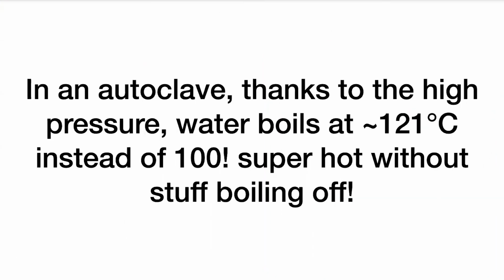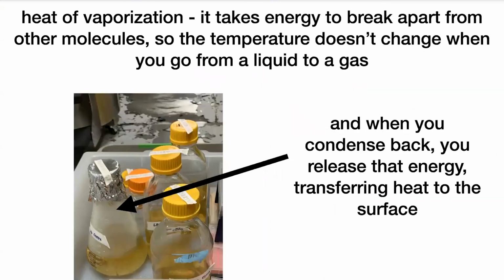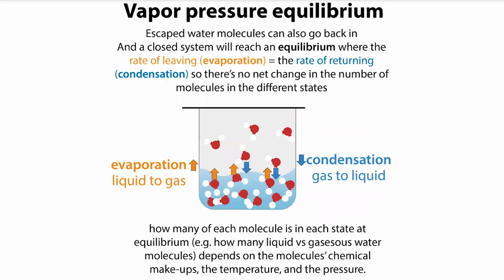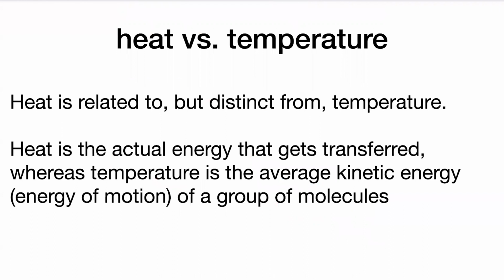But what's happening in an autoclave too is you have this closed system. This means that as you have the evaporation, you're going to get to this equilibrium where the evaporation, or going from a liquid to a gas, is going to be equal to the condensation, going from a gas to a liquid. And there's something special that happens when something undergoes one of these phase changes, and that's that the temperature doesn't increase. And so basically, I need to step back and talk a second about heat versus temperature.